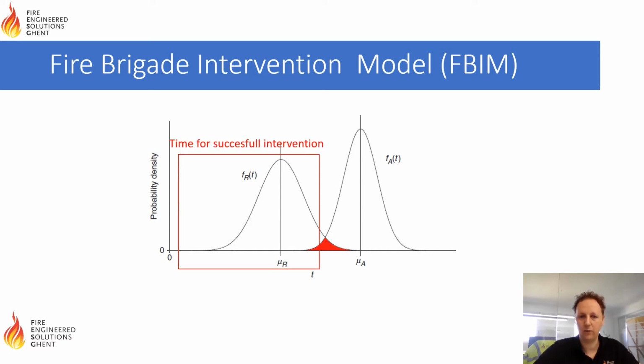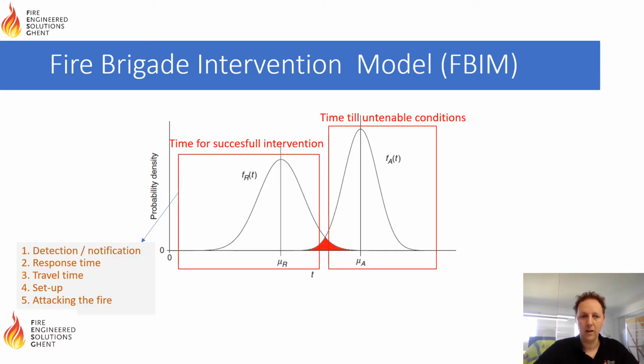The first time is a time for successful intervention, and the second time is the time till untenable conditions. Now, both of these times are depending on a lot of parameters with some uncertainties, so we're not talking about one specific time, but representing a distribution. Same for time till untenable conditions, basically how quickly the fire spreads, and from which time the fire is too large to intervene. And so what you see here is the overlap of both distributions, and that's the residual risk that by the time the fire brigade wants to put water on the fire has become too large and they cannot intervene anymore. So let's have a closer look at the first part, the time for successful intervention.